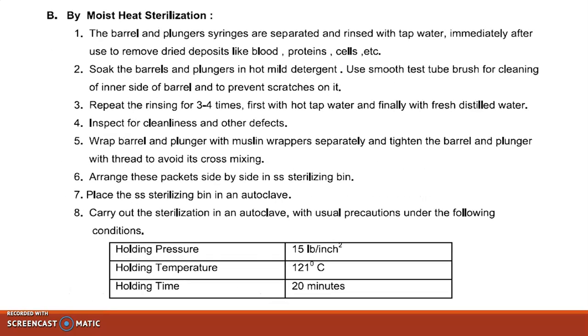Then by moist sterilization, the barrel and plunger of the syringes are separated and rinsed with tap water immediately after use to remove dry deposits like blood, protein, cells, etc. Soak the barrels and plungers in hot mild detergent. Use a smooth test tube brush for cleaning the inner side of the barrel, to prevent scratches on it. Now repeat the rinsing 3 to 4 times, similarly as we have done for the hot air oven, with hot tap water and then finally distilled water. Inspect for cleanliness and other defects.